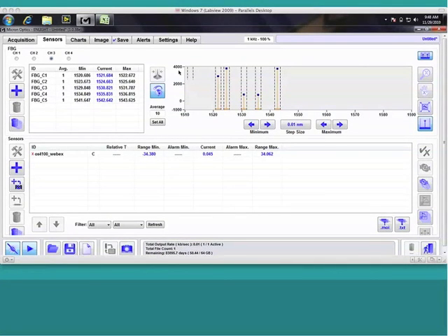The reason is that when you created it offline and then hooked up to the system later, you'll need to re-zero your sensors, and that can cause a little bit of confusion when you first connect and see these large values. But just know the reason is when you're creating offline, Enlight doesn't have a way to know what that value is, so it tries its best by using the center of the wavelength bin.